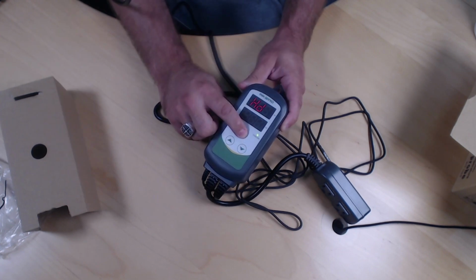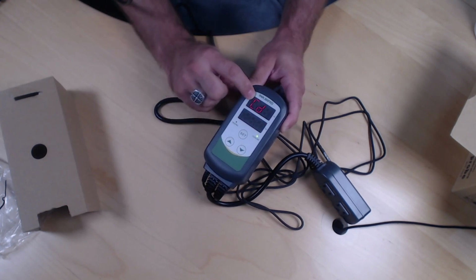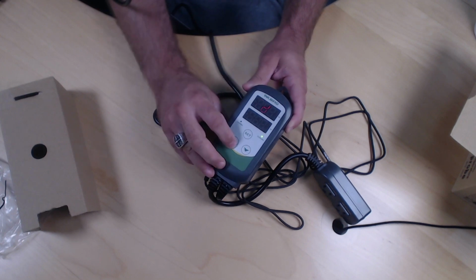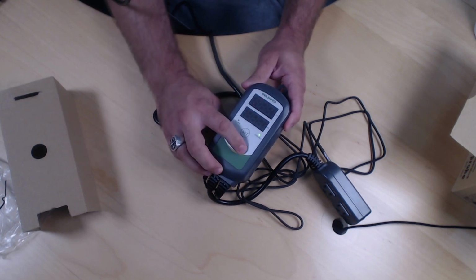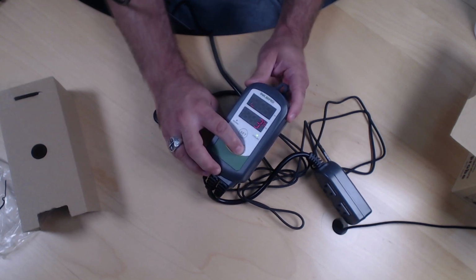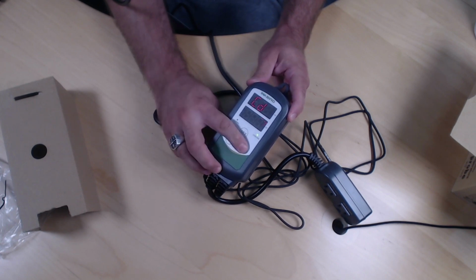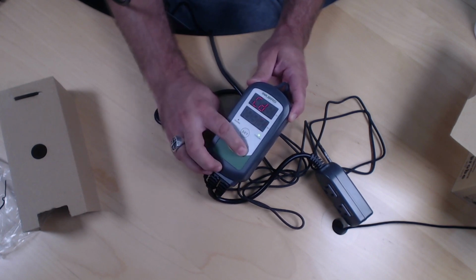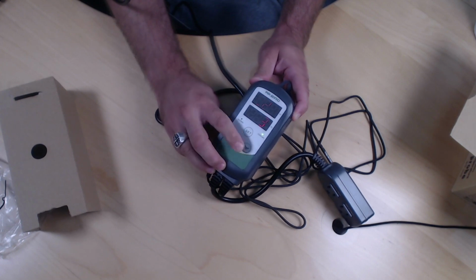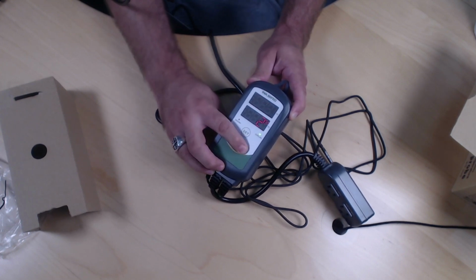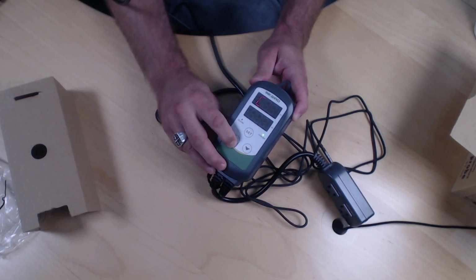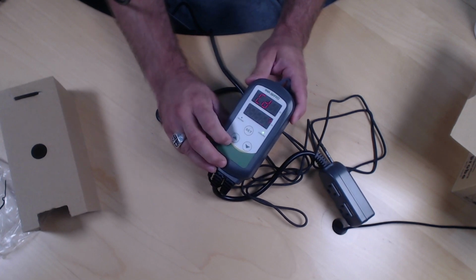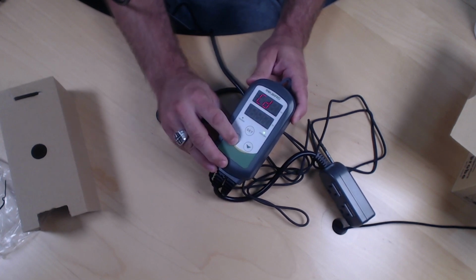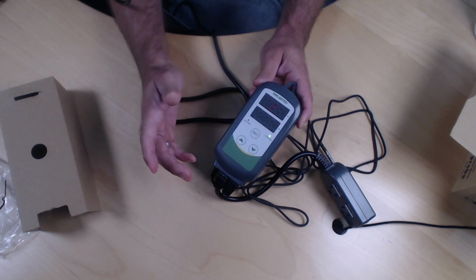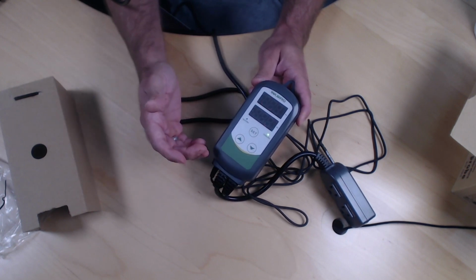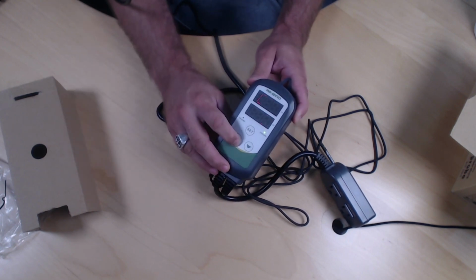Moving on, like I said in my brief rambling, the next setting is cooling difference. I think y'all kind of understand that part, but they had it at 3 degrees differential. I think 3 is probably a safe bet. I'm just going up and down with the arrows, mostly so it doesn't put me back in operation mode. It works the exact same way as heating difference does, as in when do you want the cooling side device to be turned back on? So I think 2 or 3 degrees variance above target temp is probably the best setting here, which is why they did it.